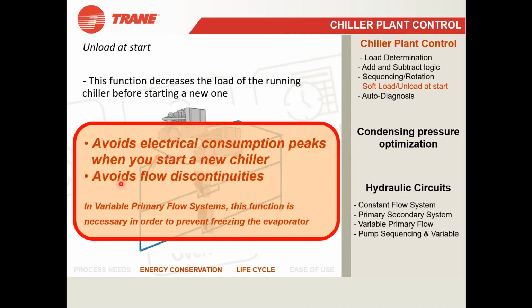Then I will go to another important parameter, which is that it should avoid flow discontinuities. You know, for a chiller, if flow discontinuity is happening, that is a very serious condition. I will describe this in another slide also, but I want to just touch base on this. If there is no flow at all, then what will happen? There is a chance that your evaporator freezing can happen.